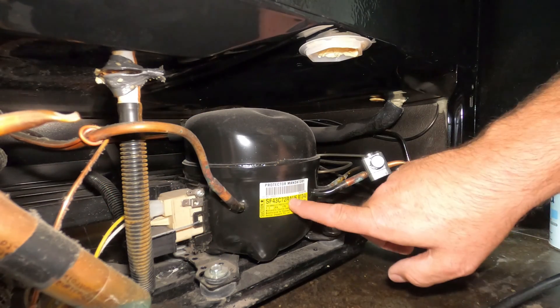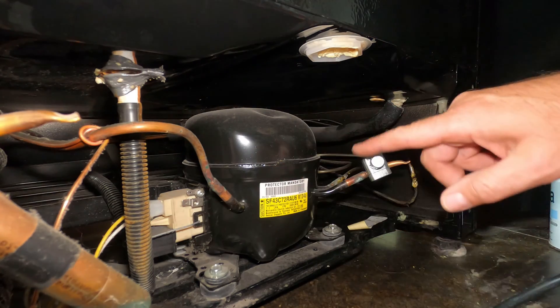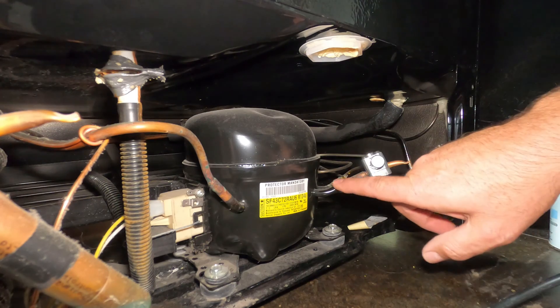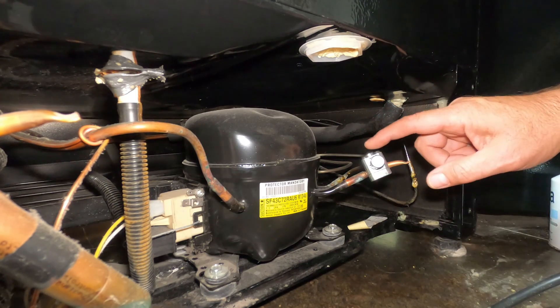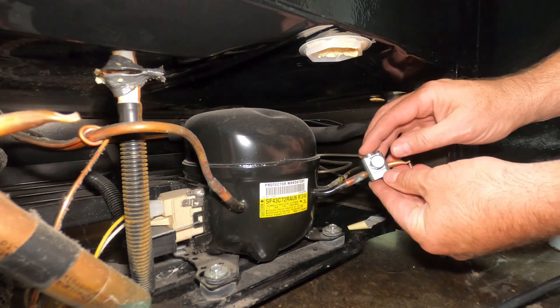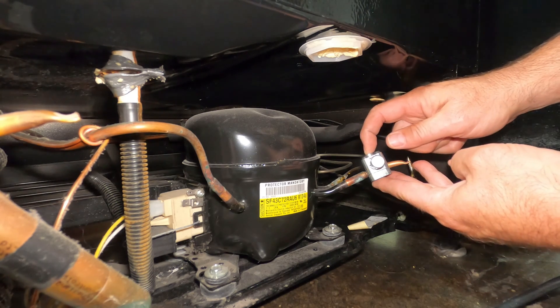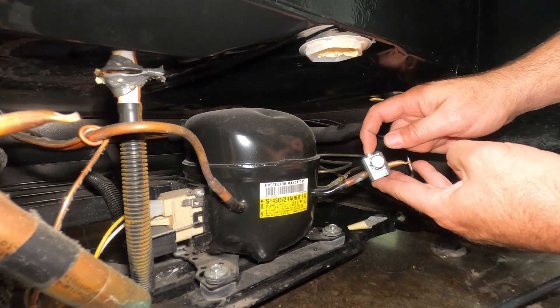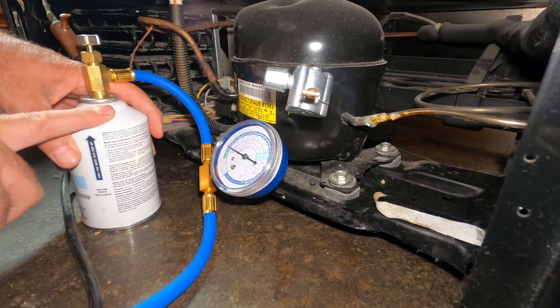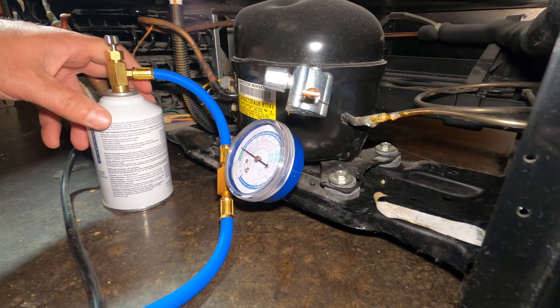If we look over here on our compressor, you can see this line comes out — this is where we connected our bullet piercing valve. There are no normal connections on our cooling lines to check your coolant level, but right here we can check the correct pressure and level by installing our bullet piercing valve. We put the bottom plate on, tightened up these Allen screws, and closed down on the piercing valve — it is sealed now. I bought this on Amazon, just like I bought this gauge and the bullet piercing valve, and I should have links to all those in the description.